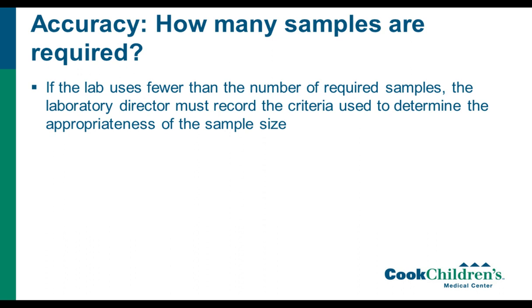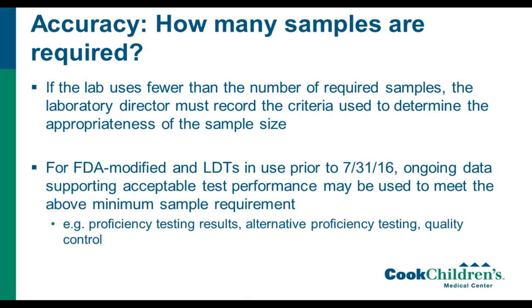If you don't have 20 samples, for assays that have less common analytes, you can use fewer than that. If you do, the laboratory director must write down, and it must be in writing, the criteria used to determine the appropriateness. So if you only have 10, the lab director has to sign off on why that's acceptable and why you couldn't get any more samples.